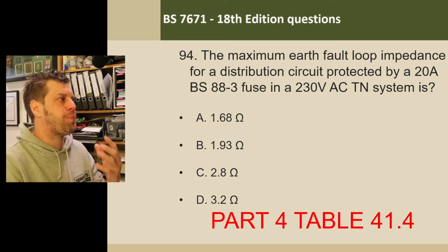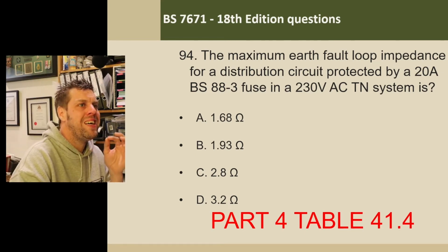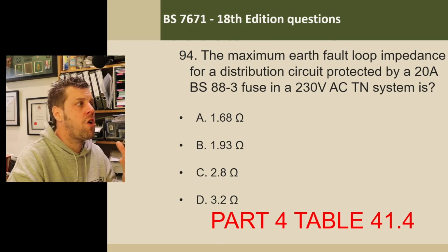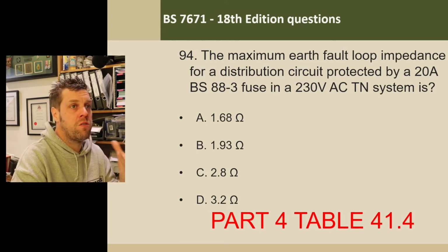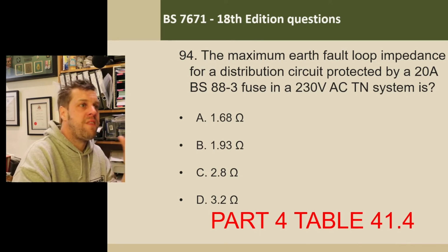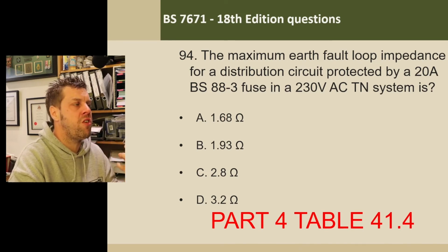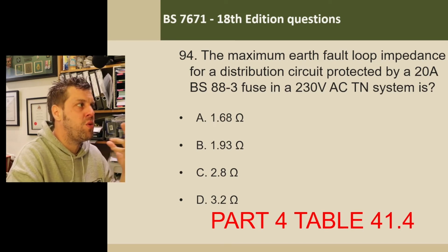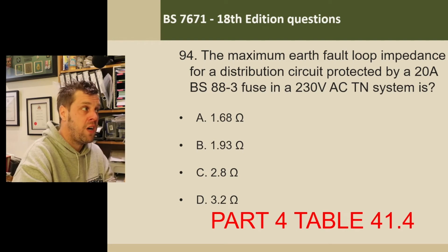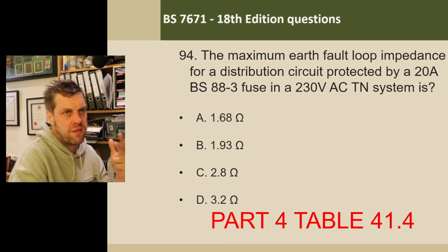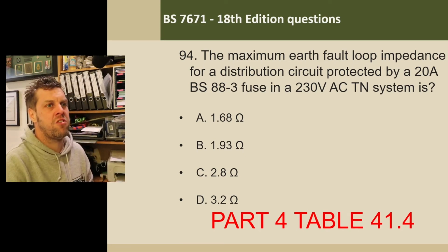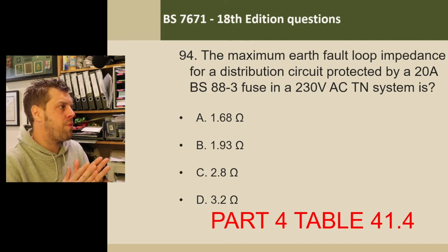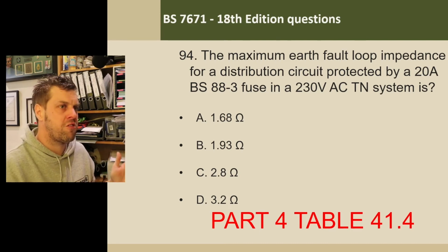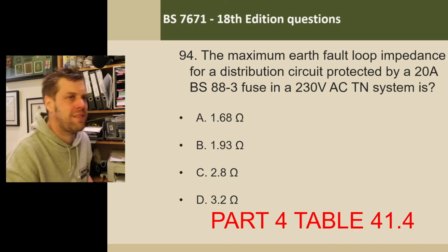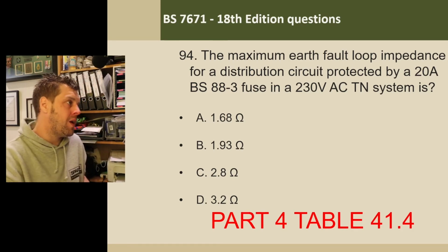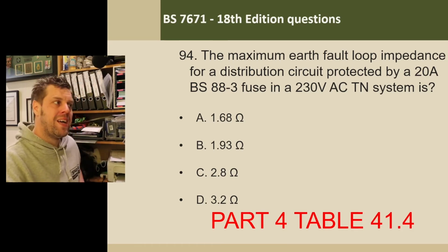That's how I got there. I put that question because there's a lot to take in. There's a lot of question there. It wants the maximum earth fault loop impedance for a distribution circuit, which makes a massive difference between a final circuit and a distribution circuit because one is 5 seconds, one is 0.4 seconds. The fuse type makes a difference. The voltage and the current of the break of the protective device all make a difference. You've got about 6,000 things in there. You've got a cross-reference against a table within 2 minutes. Can you do it? Of course you can.